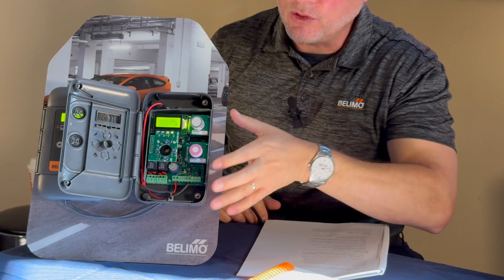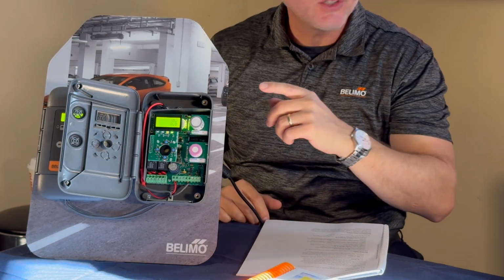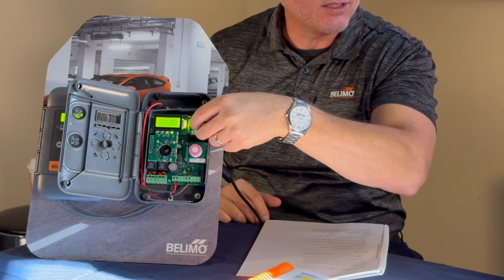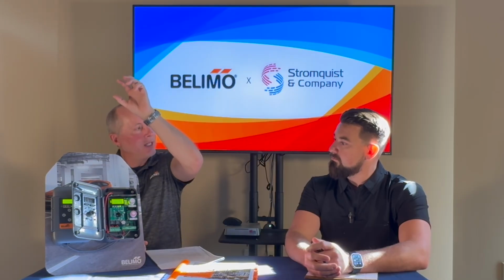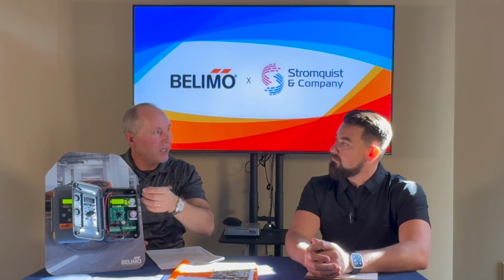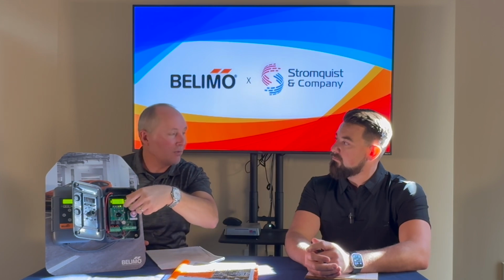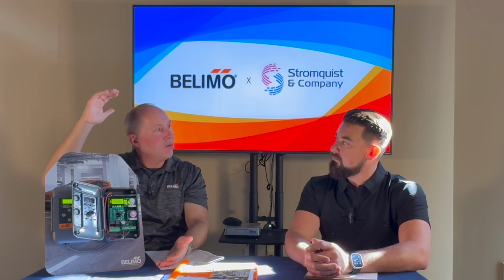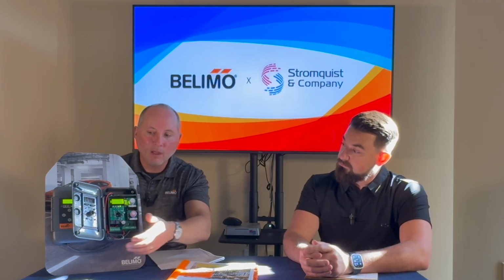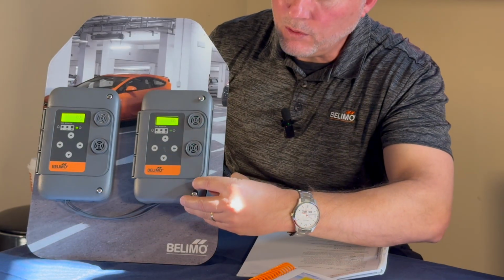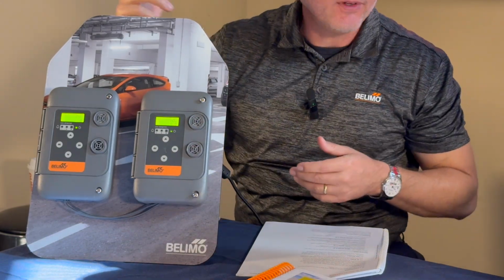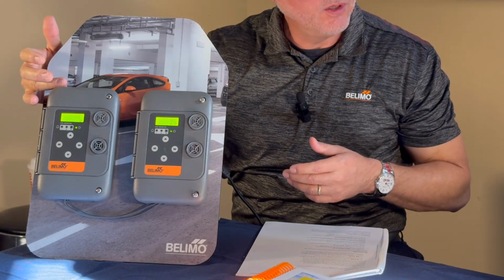So when that happens, you buy the kit but don't have to buy a new sensor. You simply take out the NO2 sensor and put it in the kit. We provide the wire to bring it down, and the module fits right in. That's how you set up the high-low kit for NO2 and CO. We also have sensors for air quality, CO, and CO2, and those are in the catalog on the website.